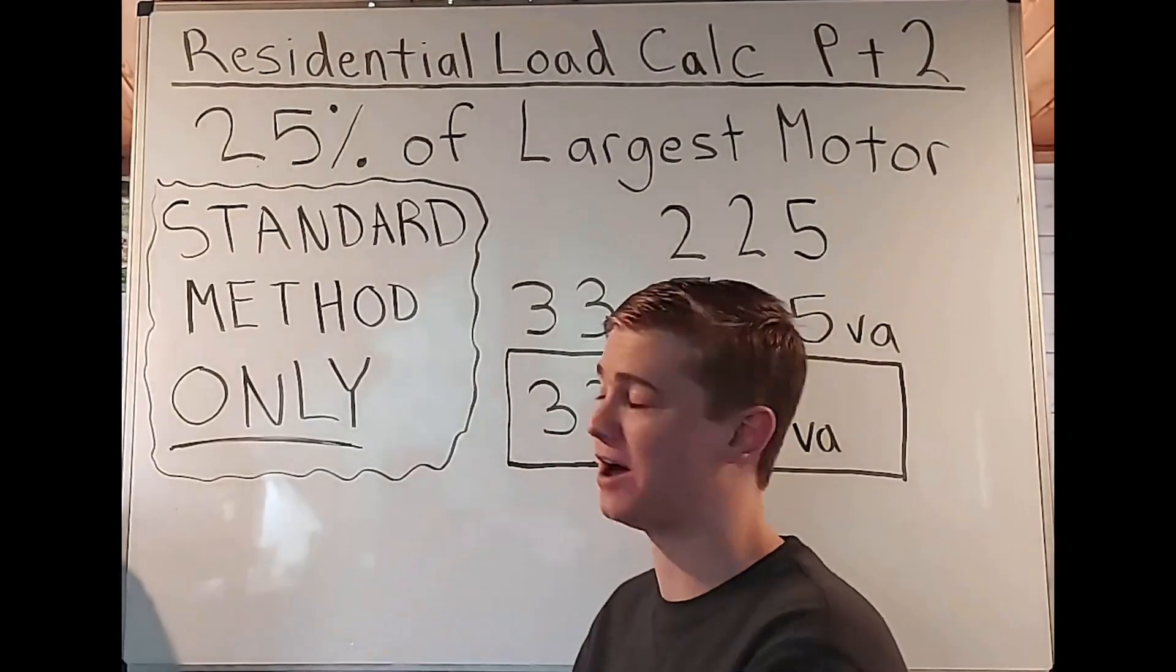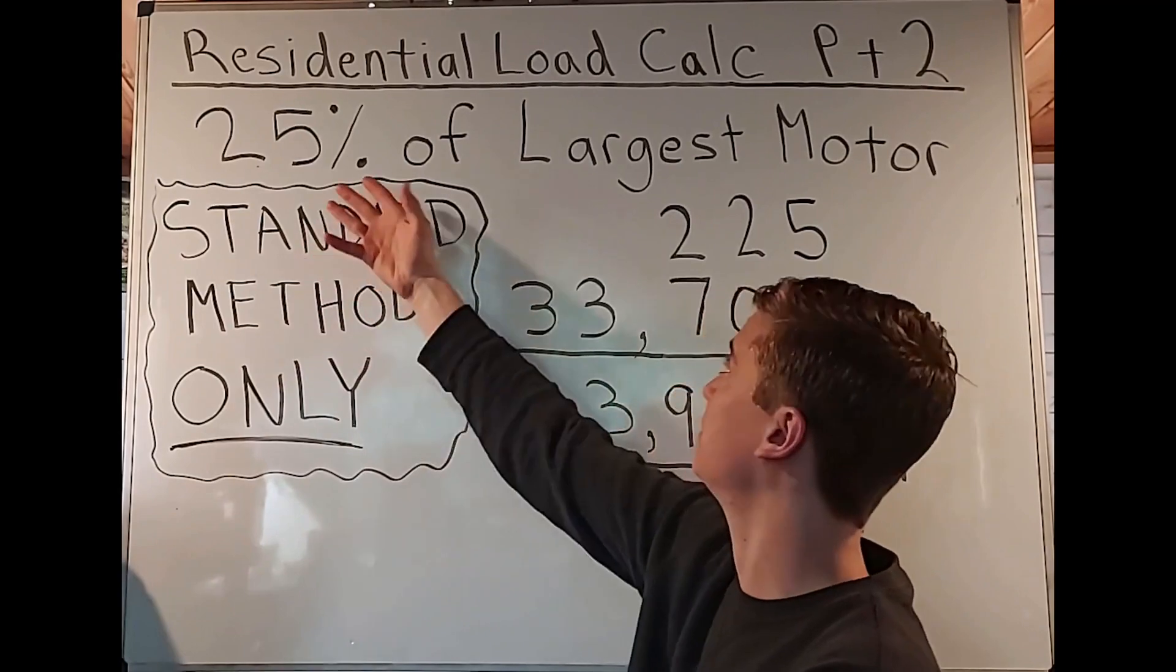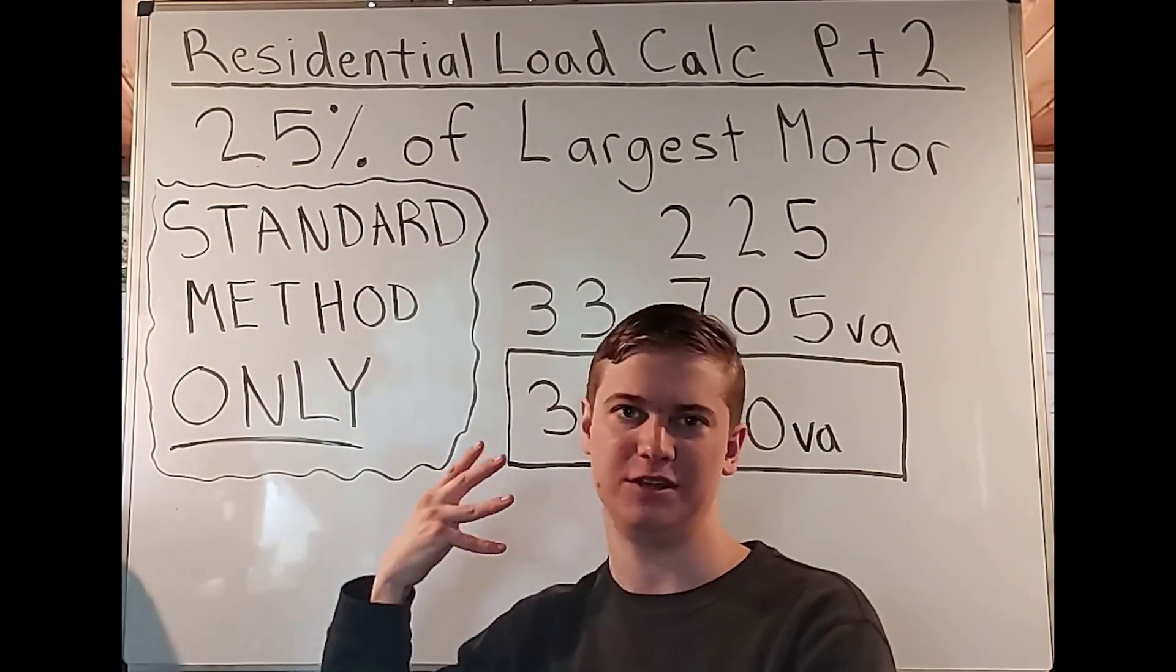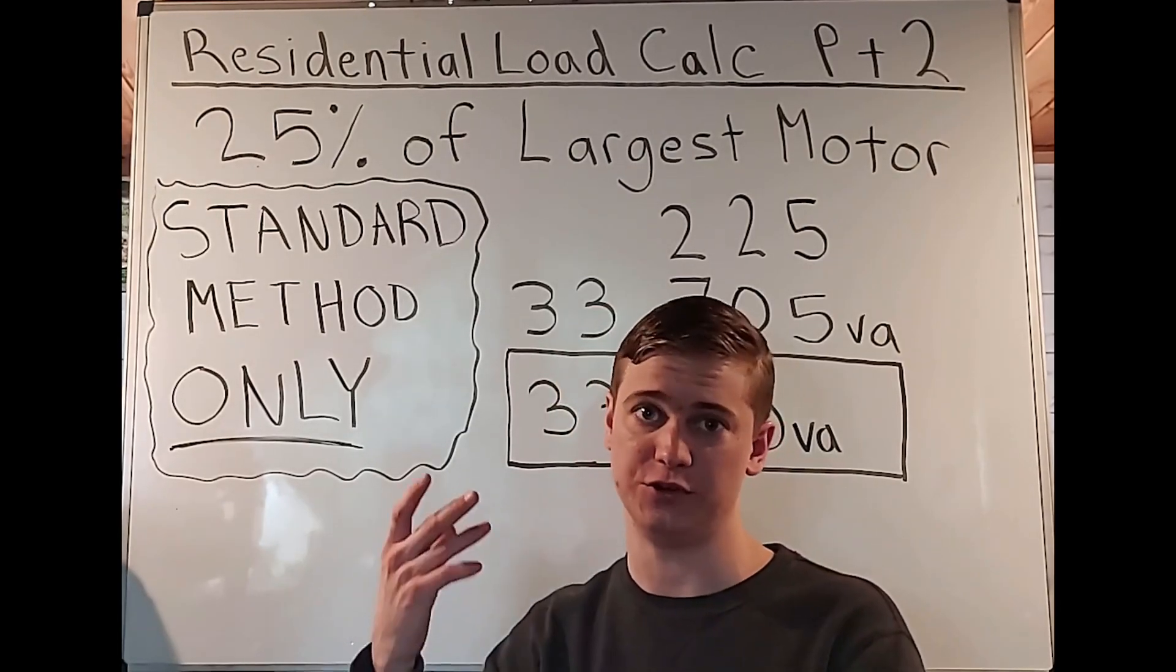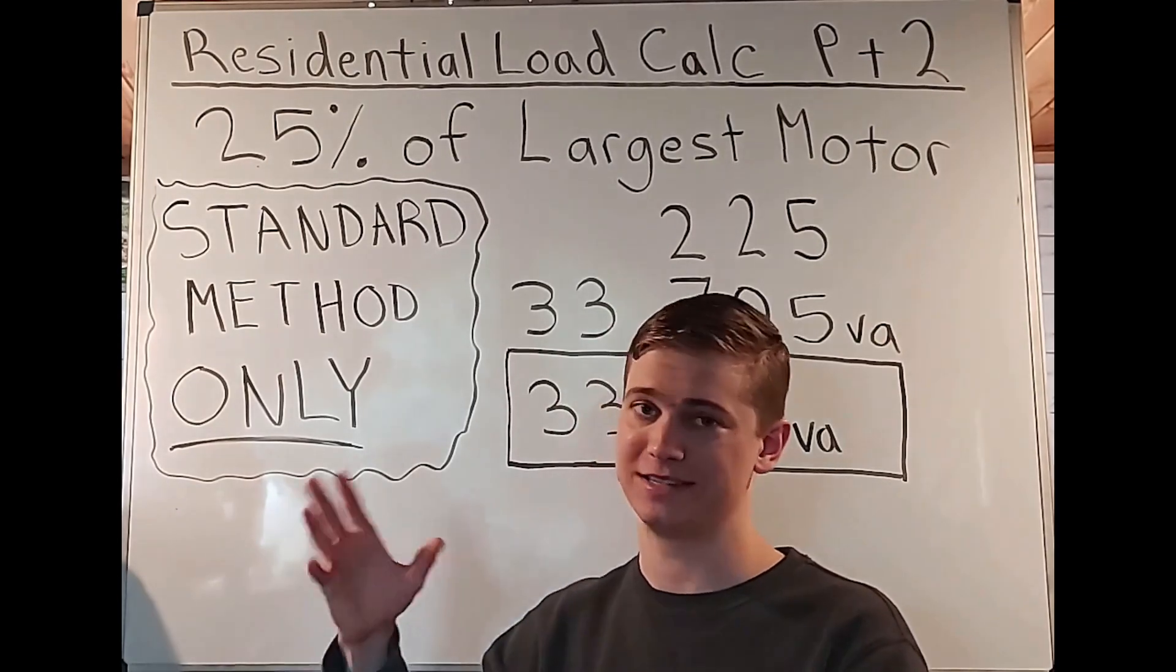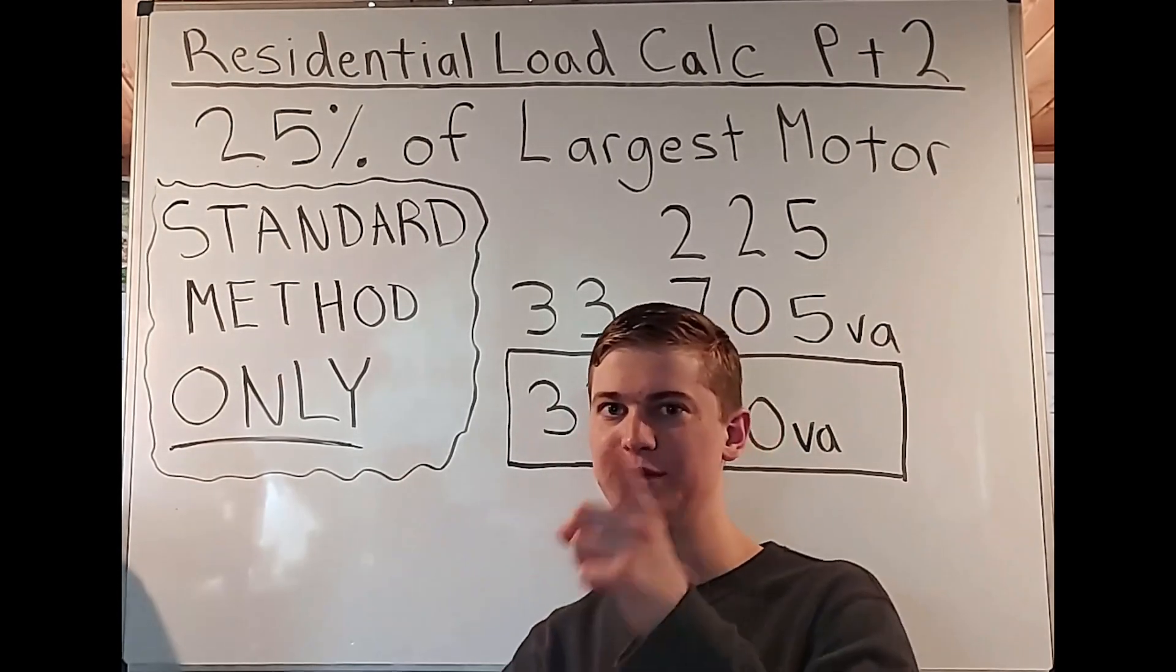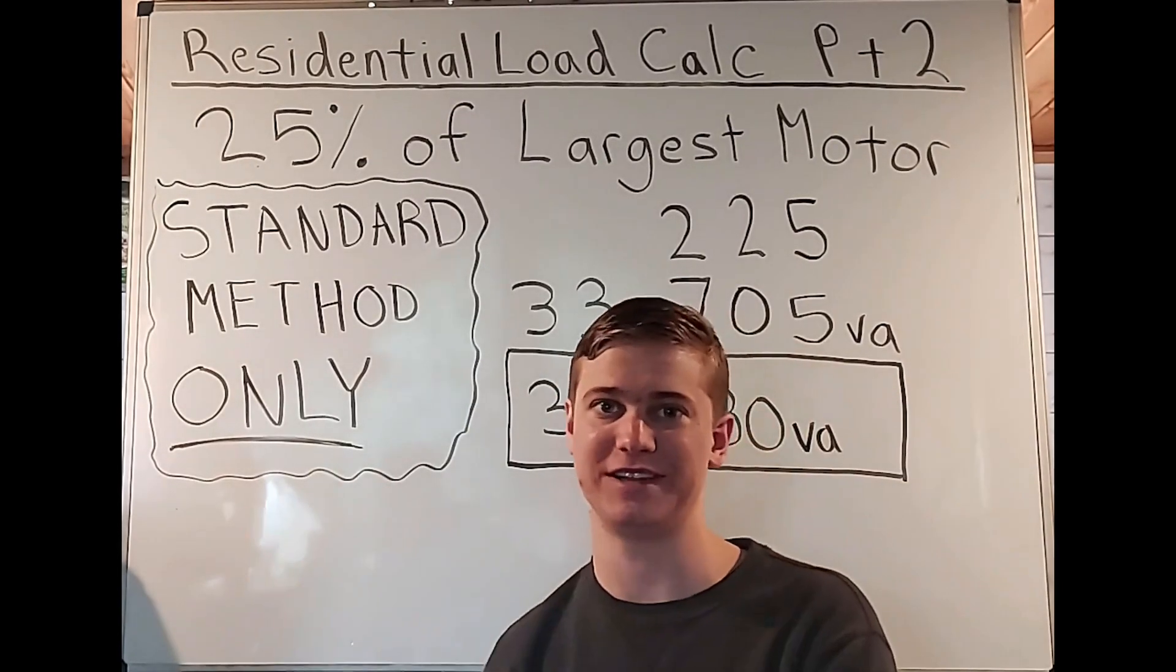And then the next thing to really comprehend here is that this is for the standard method only that you're going to be doing the 25% of the largest motor with the optional method, you don't do this. Make sure to know your optional method for your duplex and your multifamily as well. It's kind of weird compared to doing your standard method. So I'm going to have videos on all this. It's really that simple.